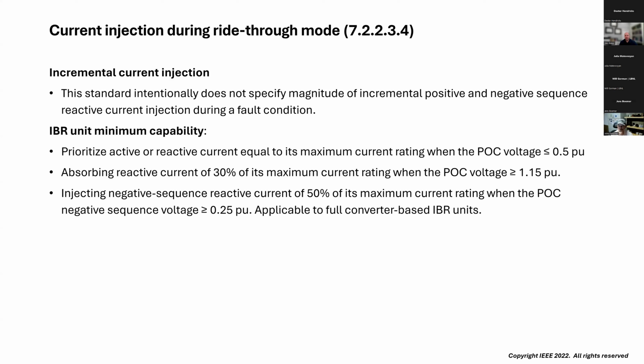But what it does say is, at a minimum capability, if the POC voltage goes below 0.5, the IBR unit needs the capability to inject either active or reactive current up to its maximum current rating. If the POC voltage goes above 1.15, it needs to absorb reactive current of 30% of the maximum current rating. And for unbalanced faults, if the POC voltage goes to 0.25 in the negative sequence, it needs the capability to inject negative sequence reactive current up to 50% of the maximum current rating.